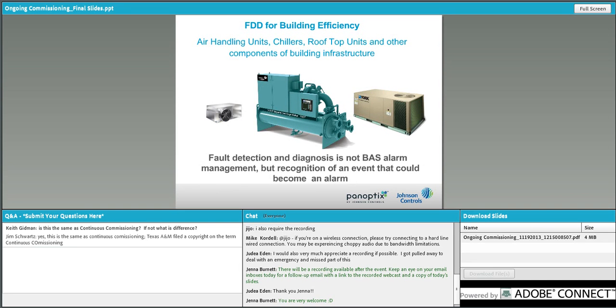So FDD is applied to all types of building systems. It's rules-based: there's a library of rules, with the ability to alter conditions so that breaking a rule triggers a fault notification of some sort. Rule sets are created to integrate multiple fault reports, such as suppressing a load if there are any faults reported from a source serving the load. A good example of this is a chiller plant. Let's say a condenser water pump fails and the chiller plant drops off, and now all the air handlers are going to start to fault out. But it's not the fault of the air handlers, it's the fault of the chiller plant. FDD would be able to put all this together, connect the dots, and suppress the faults from the air handlers, knowing that the primary fault is at the chiller plant.